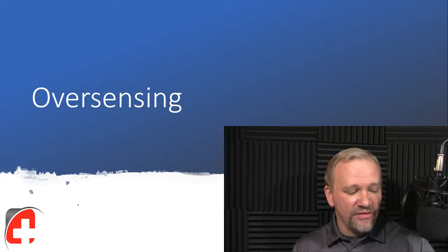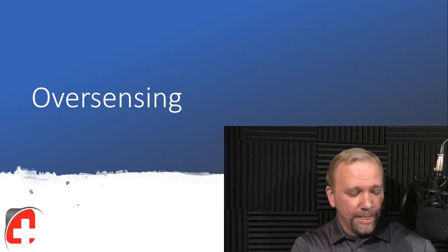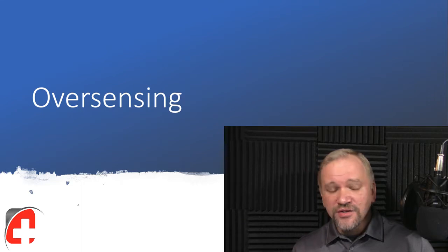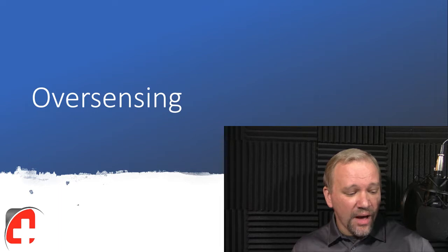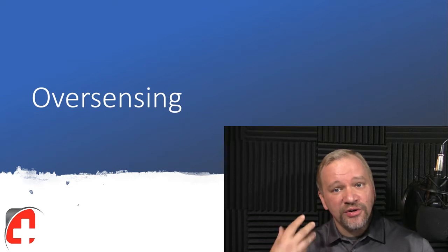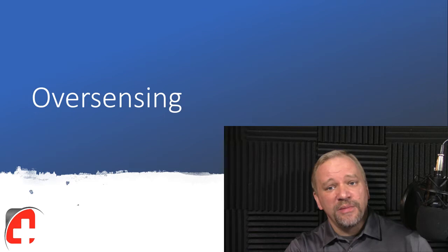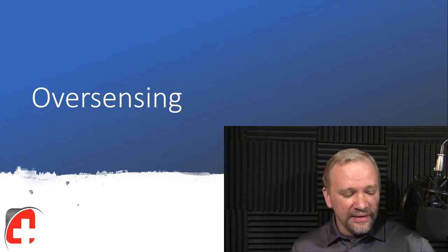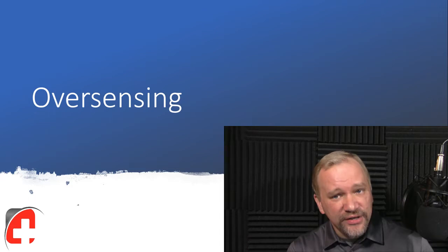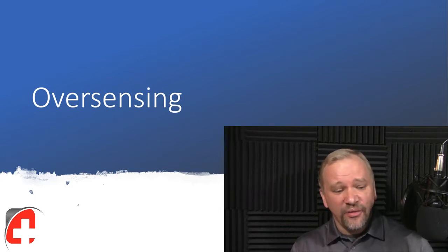So oversensing, you could have a fracture that introduces the noise, like we were talking about, and that's one of the more common causes of oversensing. You could have a reentrant complex, sort of like the pacemaker-mediated tachycardia, that causes it to sense the electrical depolarization activity. Now, the pacemaker has no way of knowing whether this is associated with any mechanical activity, and there's really no way for it to tell. Its job is to sense electrical activity, and it does that very well.